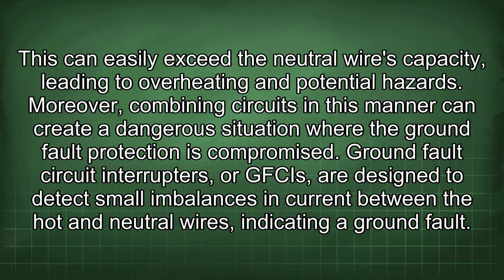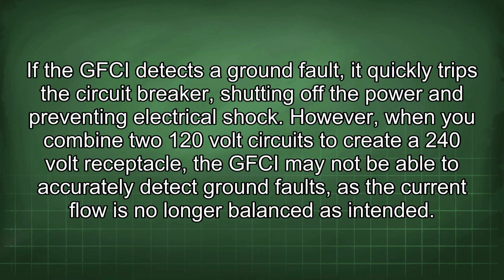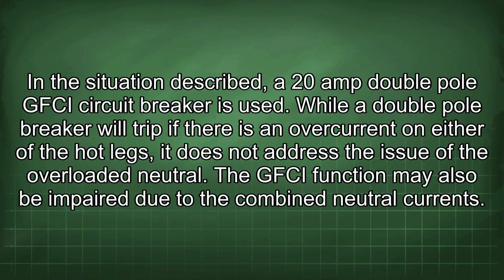Ground fault circuit interrupters, or GFCIs, are designed to detect small imbalances in current between the hot and neutral wires, indicating a ground fault. If the GFCI detects a ground fault, it quickly trips the circuit breaker, shutting off the power and preventing electrical shock. However, when you combine two 120-volt circuits to create a 240-volt receptacle, the GFCI may not be able to accurately detect ground faults, as the current flow is no longer balanced as intended. In the situation described, a 20-amp double-pole GFCI circuit breaker is used. While a double-pole breaker will trip if there is an overcurrent on either of the hot legs, it does not address the issue of the overloaded neutral. The GFCI function may also be impaired due to the combined neutral currents.